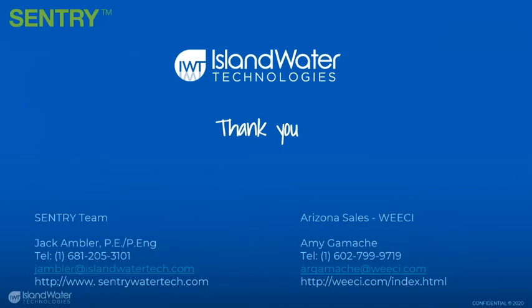Sure, it's a UV and a UV visible sensor. So it measures from 256 to 750 nanometers. So it's measuring the whole visible and invisible range. And then from that, they actually can calculate the organic as well as inorganic loading.